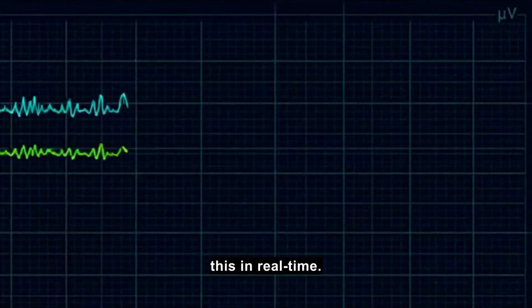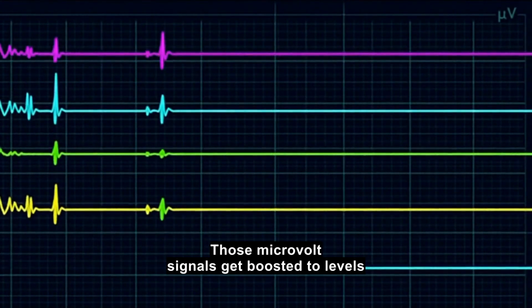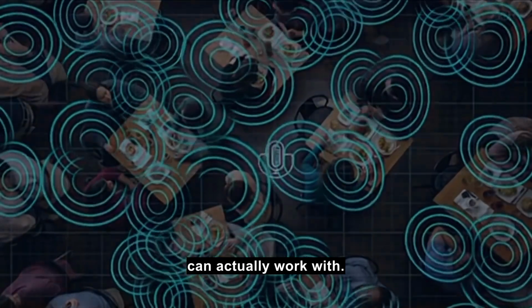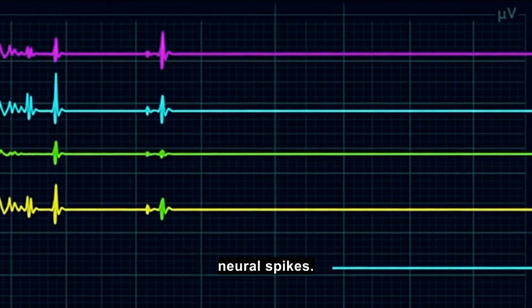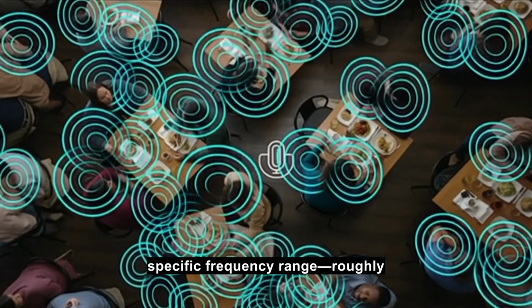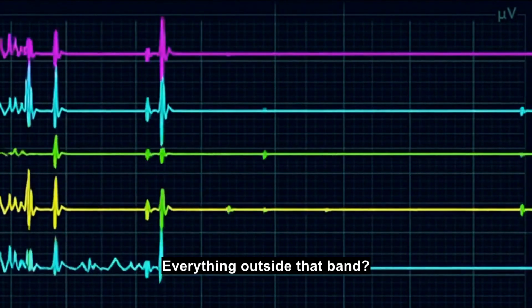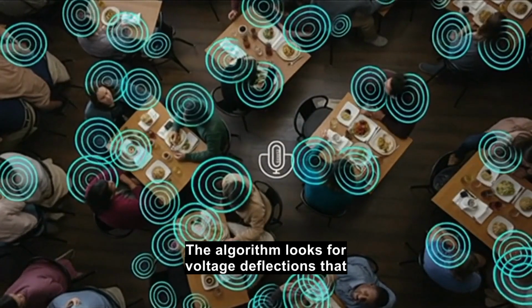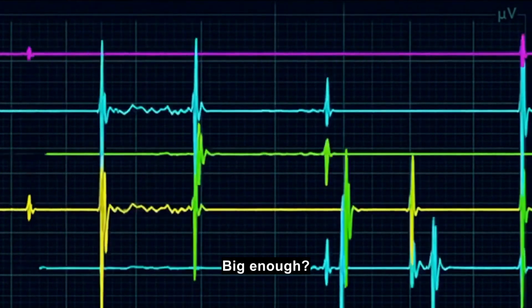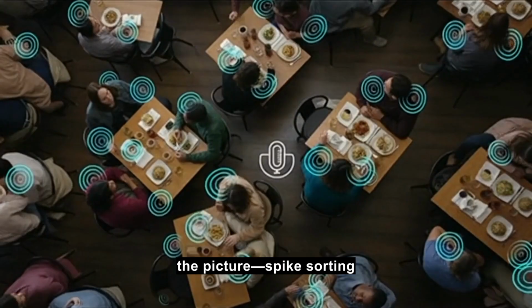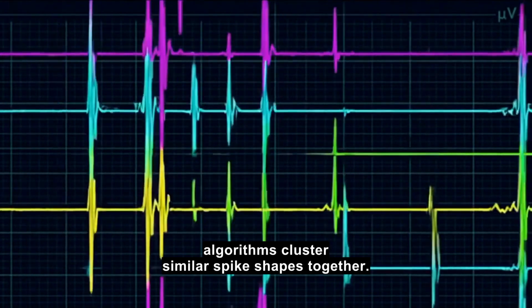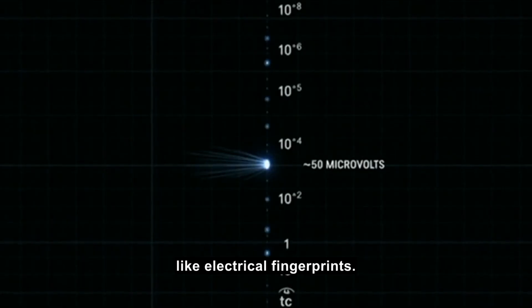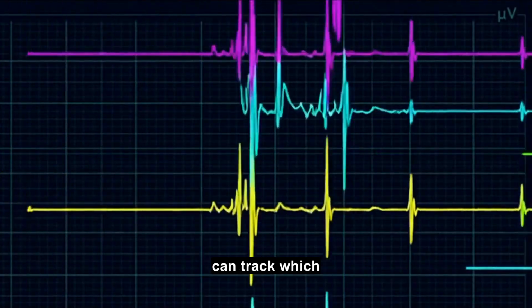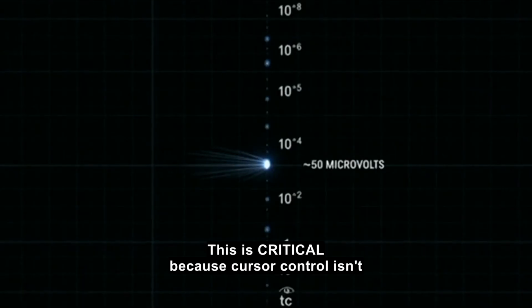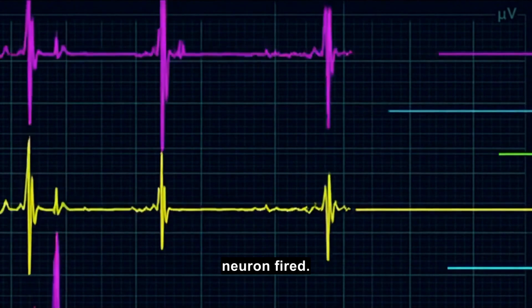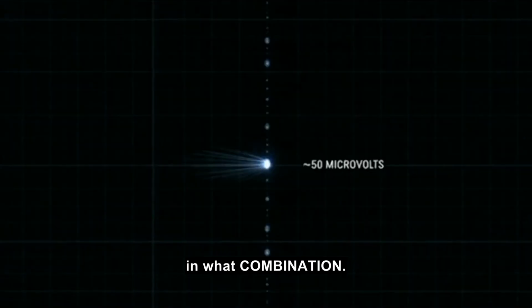First, amplification. Those microvolt signals get boosted to levels that the electronics can actually work with. Second, bandpass filtering. This removes frequencies that aren't relevant to neural spikes. Action potentials typically show up in a specific frequency range, roughly 300 to 3000 Hz. Everything outside that band, filtered out. Third, threshold detection. The algorithm looks for voltage deflections that exceed a certain amplitude. Too small? Probably noise. Big enough? Probably a spike. Fourth, and this is where machine learning enters the picture, spike sorting algorithms cluster similar spike shapes together. Different neurons have subtly different spike signatures, like electrical fingerprints. By sorting spikes into clusters, the system can track which neurons are firing, how often, and in what patterns. This is critical because cursor control isn't about whether a neuron fired. It's about which neurons fired, when, and in what combination.